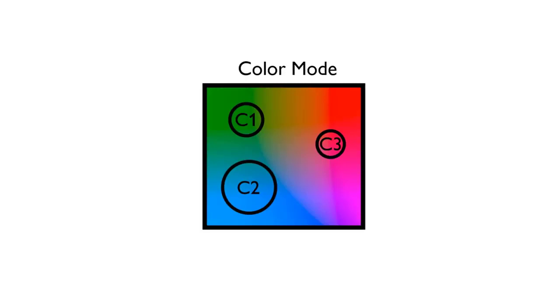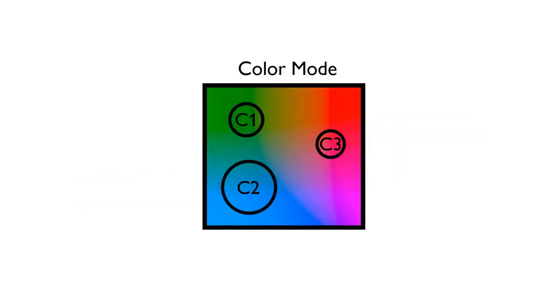Color mode. This diagram shows a color space and there's three taught colors. In the center of each circle is where each particular color was taught. The circle around that shows the tolerance setting for each color. So the sensor would switch on whenever the color is anywhere within any of those three circles.